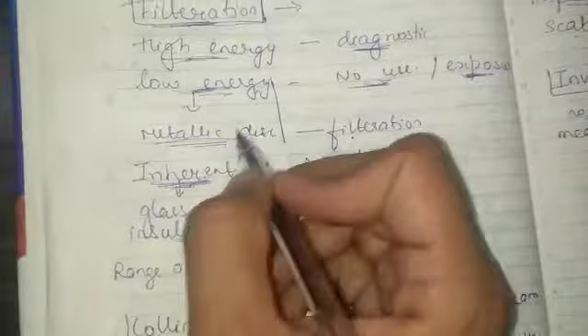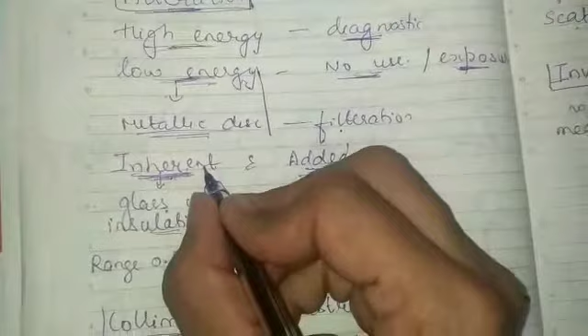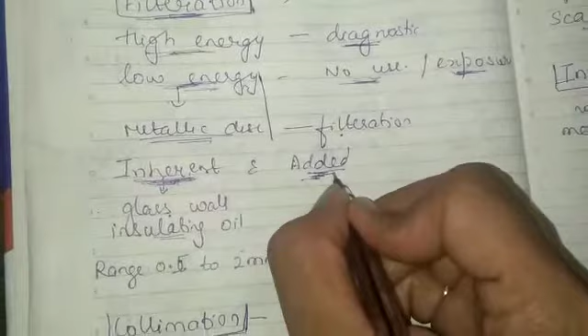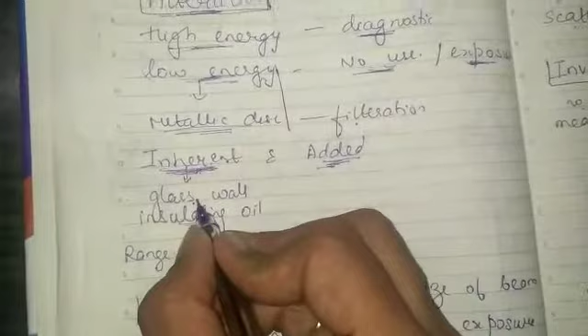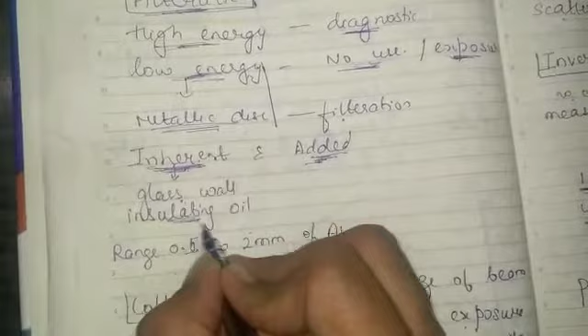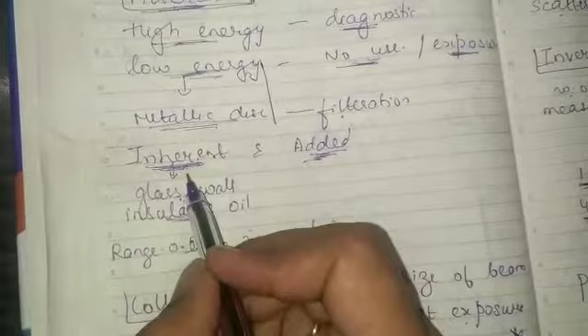So the filtrations are of two types. First is inherent filtrations. Inert filtrations are those which are already added in the X-ray tubes, and the second is added filtration, which we add. So what are inherent filtrations? Inert filtrations are enclosed in the X-ray tubes only. These are like the glass wall of an X-ray tube, or the insulating oil which surrounds the dental tubes. So they act as a barrier and they will prevent the low energy photons.